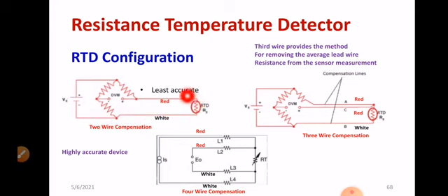As far as 2-wire compensation is concerned, this is the least accurate. If you want a little more accuracy, go for 3-wire compensation. In the case of 3-wire compensation, you can see that you are using 2 red wires and 1 white wire, and you will be arranging the Wheatstone's bridge. The third wire provides a method for removing the average lead wire resistance from the sensor measurement. Thus, it ensures the accuracy.